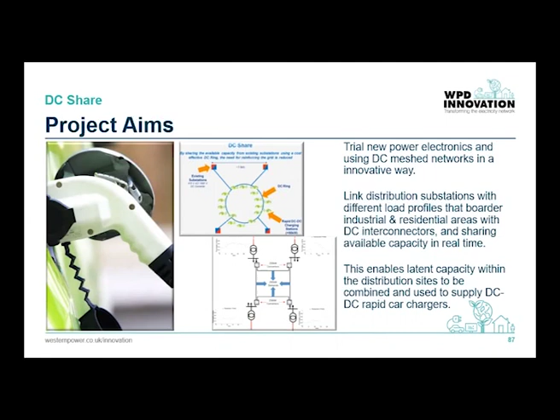If we can flex that between the two substations, we equalise that demand, and therefore that gives us more headroom to supply rapid chargers with a DC supply. By taking a little bit of capacity from each of those substations and feeding it into rapid chargers, it alleviates the need for heavy reinforcement at any individual point of the network. Conventionally, we'd have to change out the substation, and there would also be significant reinforcement on the 11 kV network to provide enough capacity. So it's a really new design and a novel way of gaining capacity from the network.